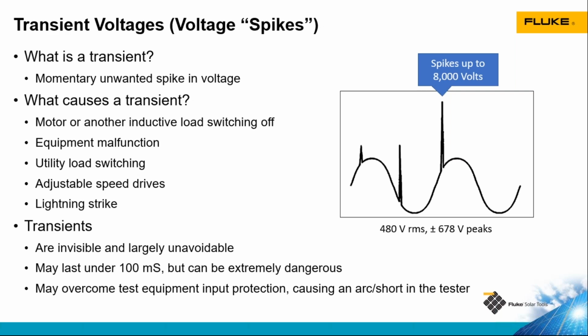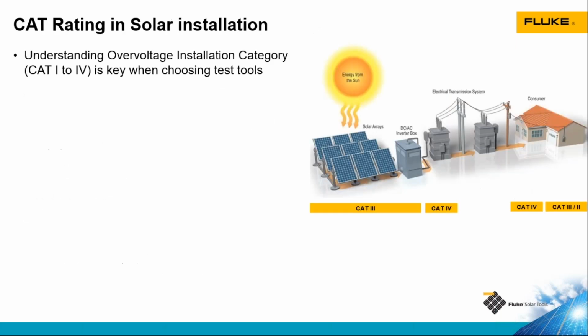We can measure transient voltage spikes with our higher end power quality analyzers if we need to record and monitor for transient voltage spikes. But the most important thing on this slide is the last bullet, and that's that if we are testing voltage at the time of transient voltage spike, that test tool needs to be able to withstand that voltage spike without causing damage to the tool, and especially without causing a safety hazard to the technician. In order to ensure that our test and measurement tools can withstand those transient voltage spikes, we need to identify the category environment in which we will be doing the testing.